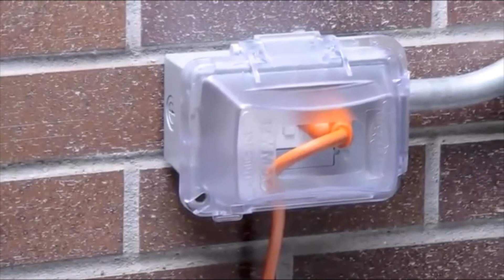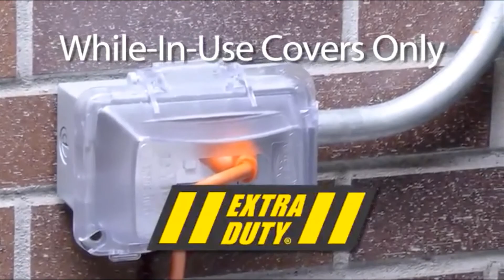Basically, all receptacles in a potentially wet location require a while-in-use cover, and it needs to meet the new UL Extra Duty rating. First generation bubble covers weren't rugged enough to meet the Extra Duty rating, so the MM420 was completely redesigned to meet the Extra Duty requirement.